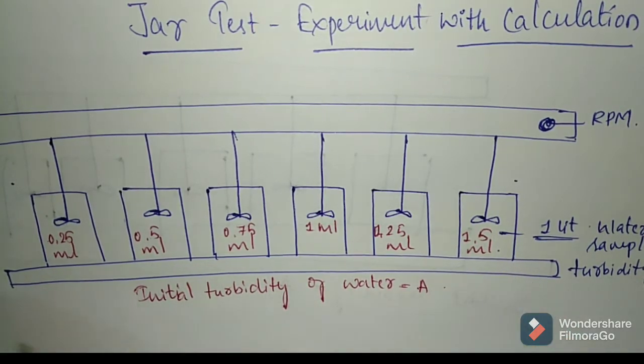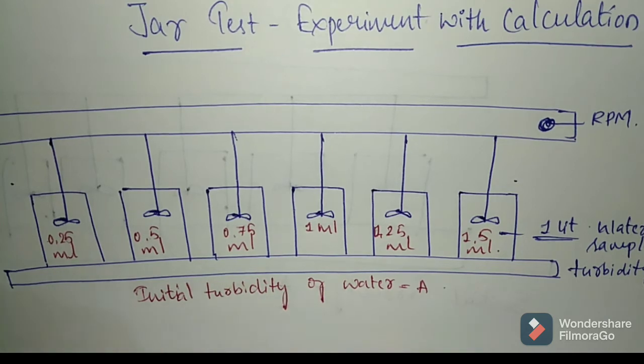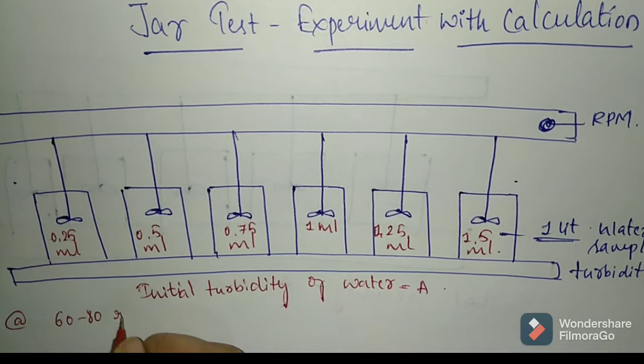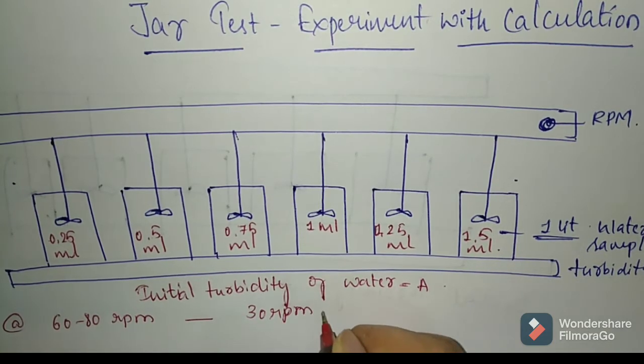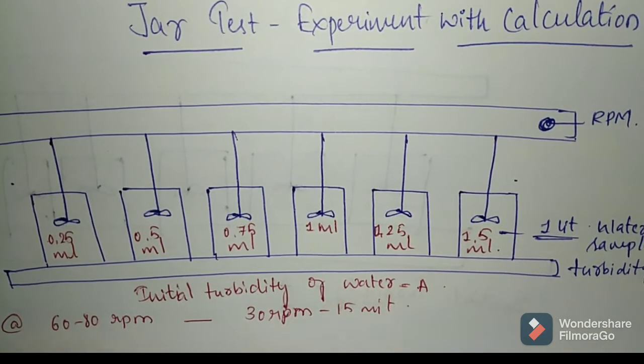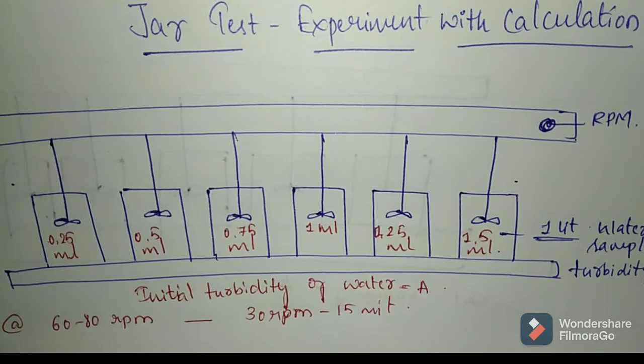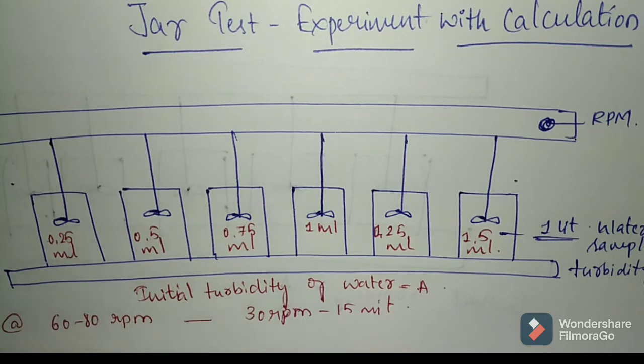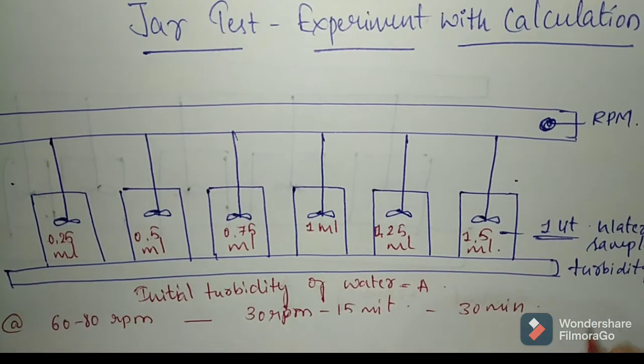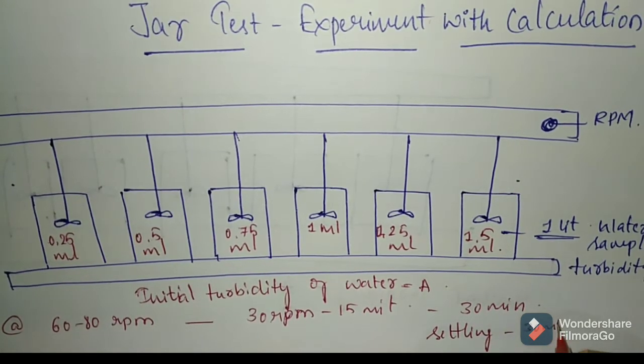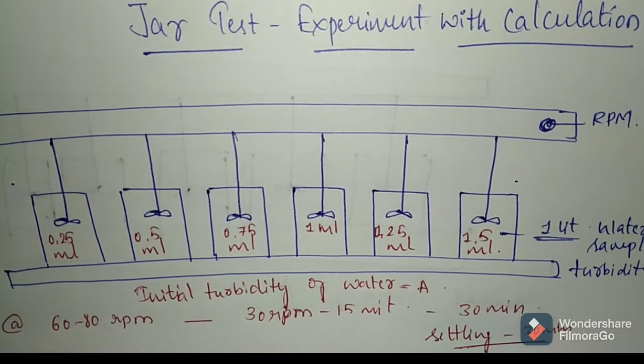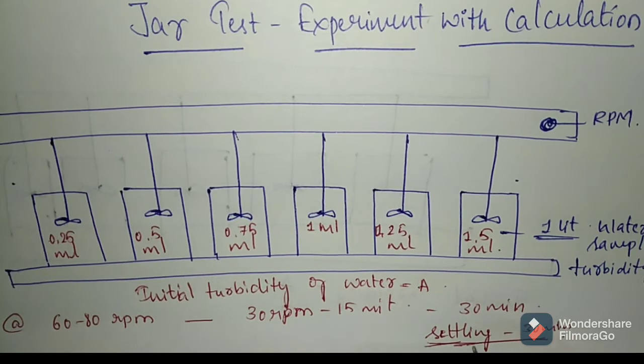After adding the coagulant dosage, we will go for flocculation. Flocculate the samples rapidly for about one minute with mechanically operated paddles at around 60 to 80 RPM, followed by gentle stirring at about 30 RPM for 15 minutes. Then remove the jars from the stirring device. Let the samples stand for at least 30 minutes for settling of the flocs. Settling is directly proportional to time.